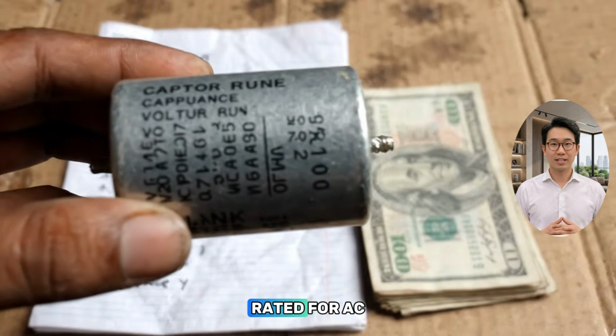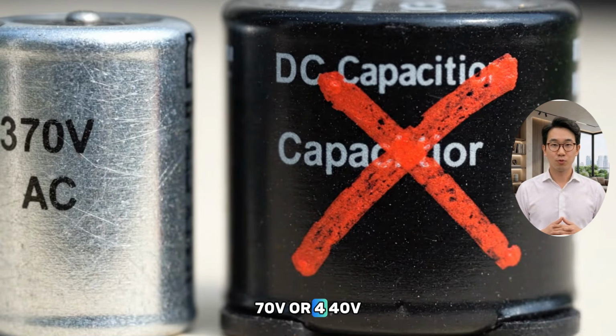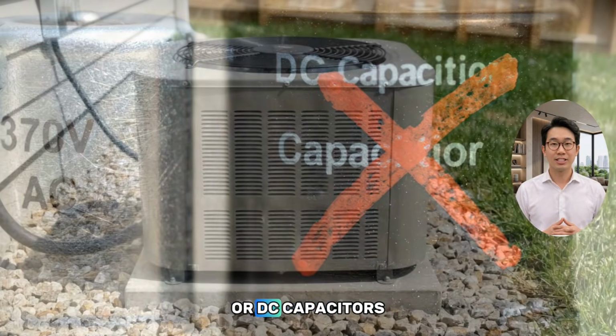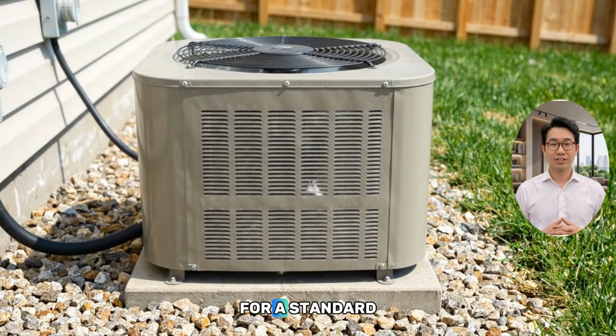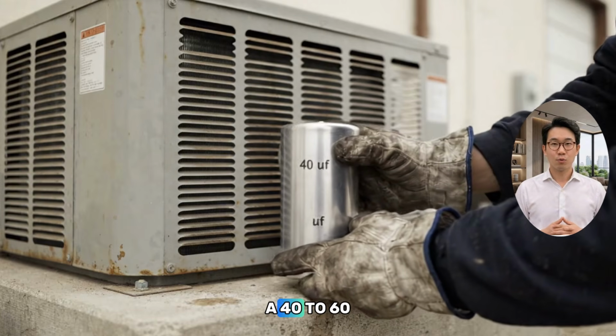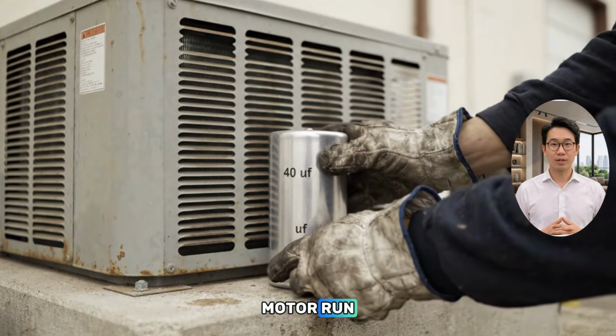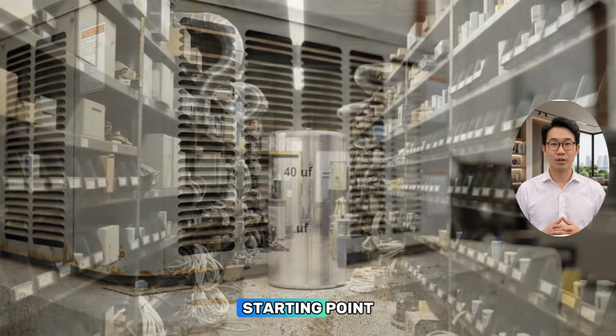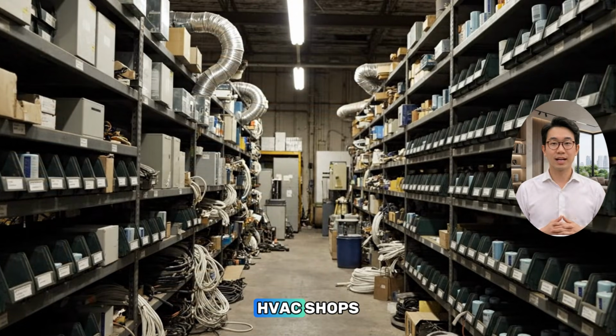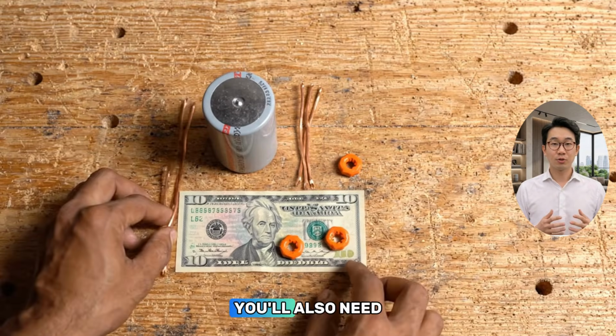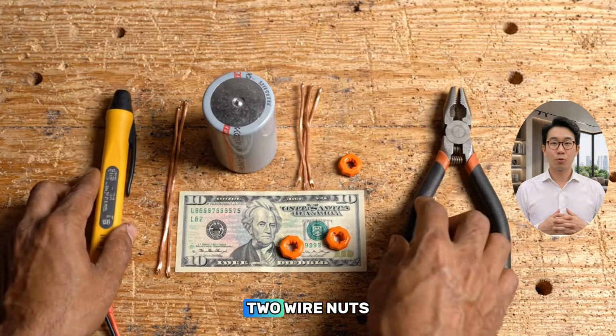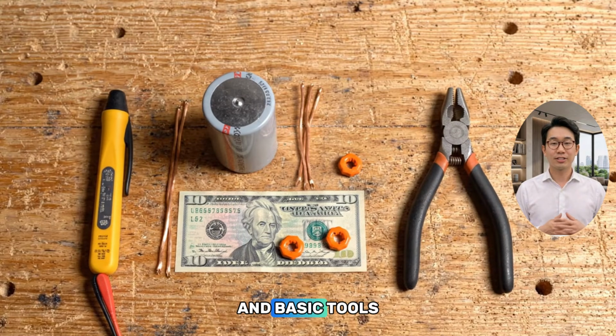Here is your shopping list. You need a motor-run capacitor rated for AC line voltage, specifically 370V or 440V AC. Never use motor start capacitors or DC capacitors. They will fail. For a standard home with central air, a 40 to 60 microfarad motor-run capacitor is the ideal starting point. You can find these at HVAC shops or online for under $10. You'll also need 2 short lengths of rated wire, 2 wire nuts, your voltage tester, and basic tools.